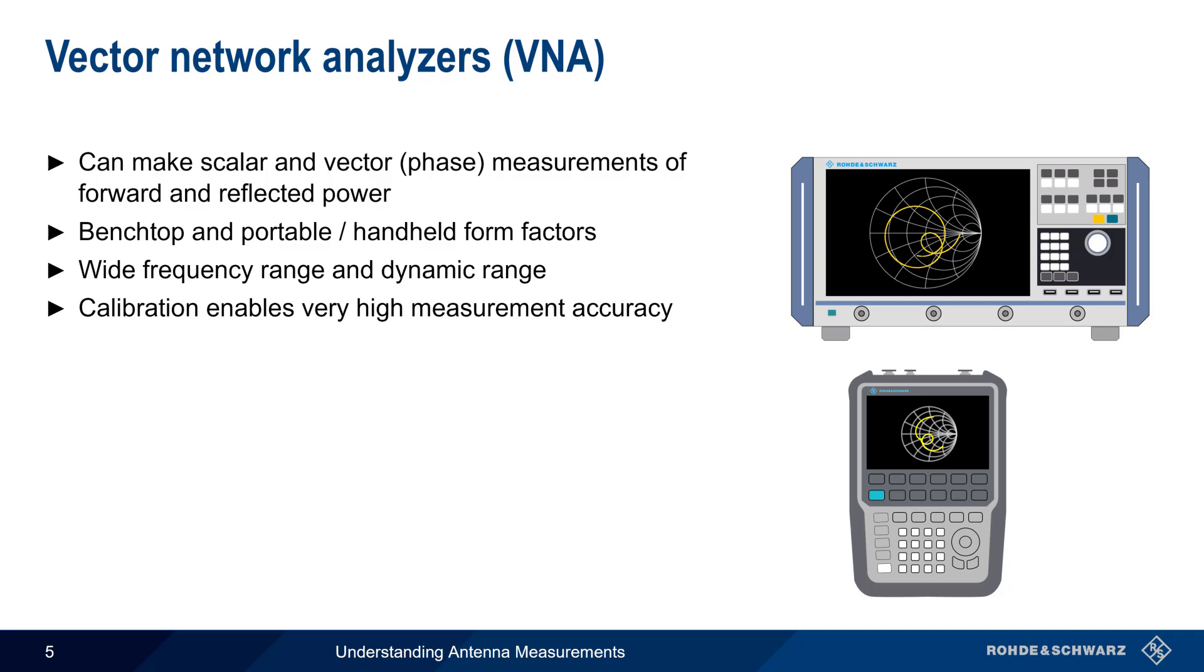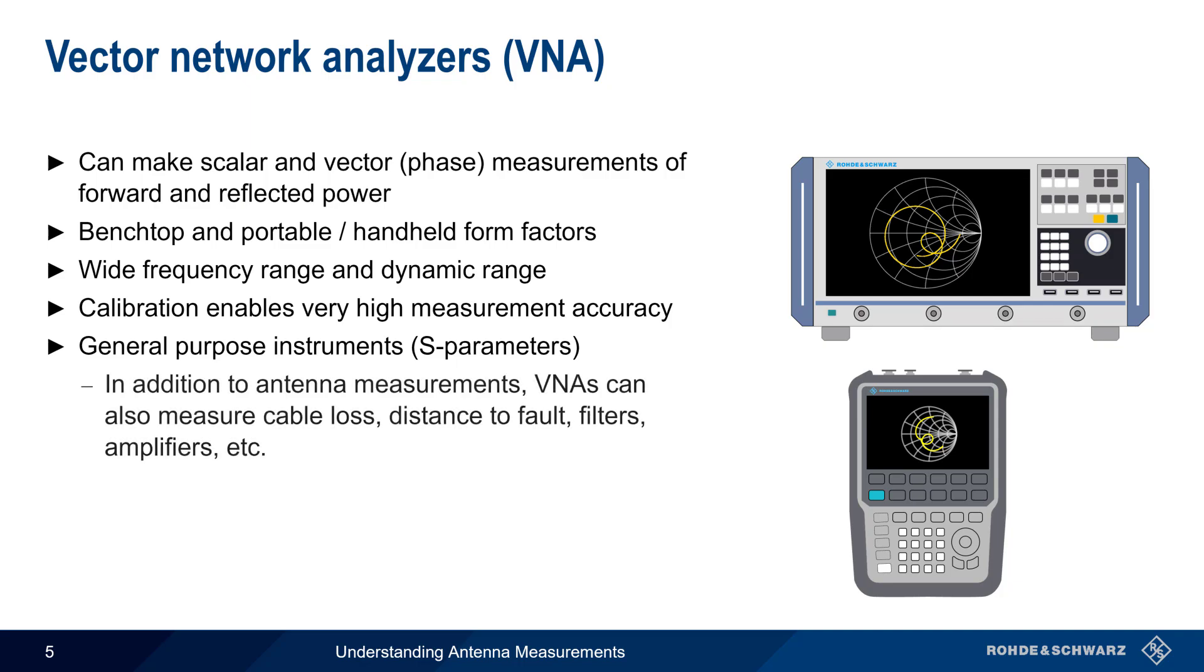Although this presentation will focus on antenna measurements, VNAs are general purpose instruments that can measure, display, and record so-called S, or scattering parameters, for a wide variety of devices and applications. This means that in addition to measuring antennas, VNAs can also be used to measure cable loss, distance to fault, filters, amplifiers, etc.